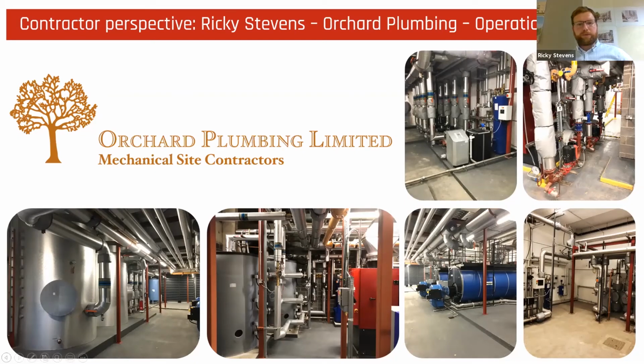Yeah, in our experience with acceptance testing as a whole, going back 4 or 5 years ago, before we came across FairHeat, there was very little done in the actual dwellings. A lot of the concentration and witnessing was actually carried out within the energy centres itself, with all the time associated in that area. When we first came across FairHeat and the acceptance testing over at Chelmsford, we had large reports come back with a number of areas failing.